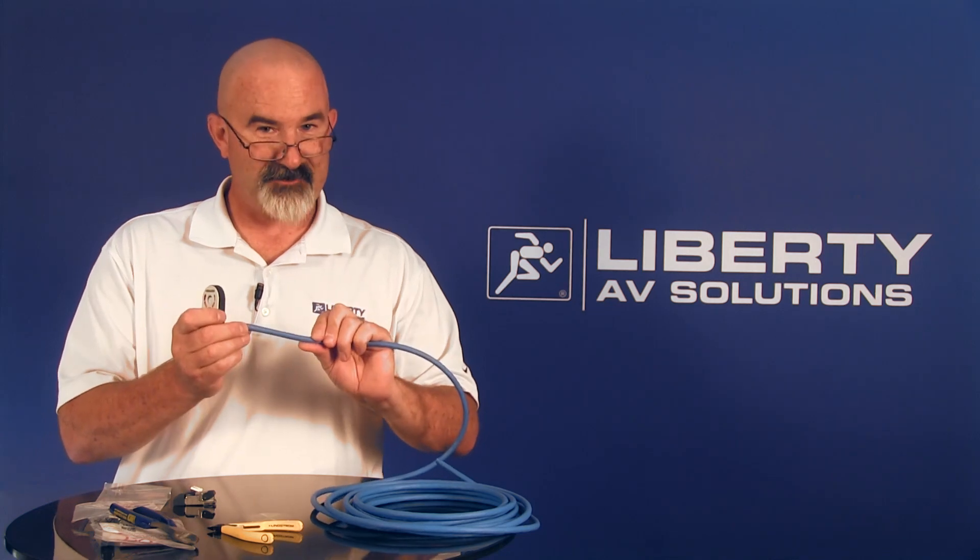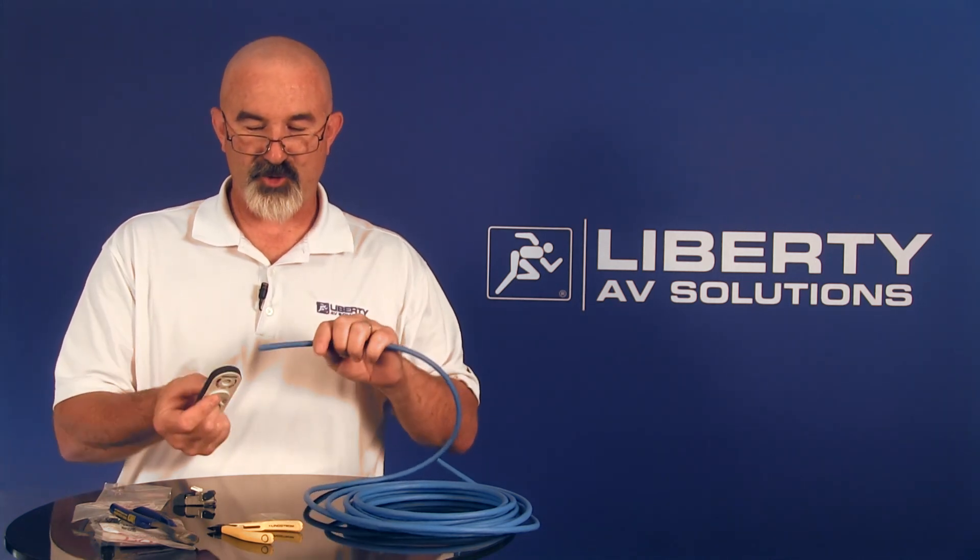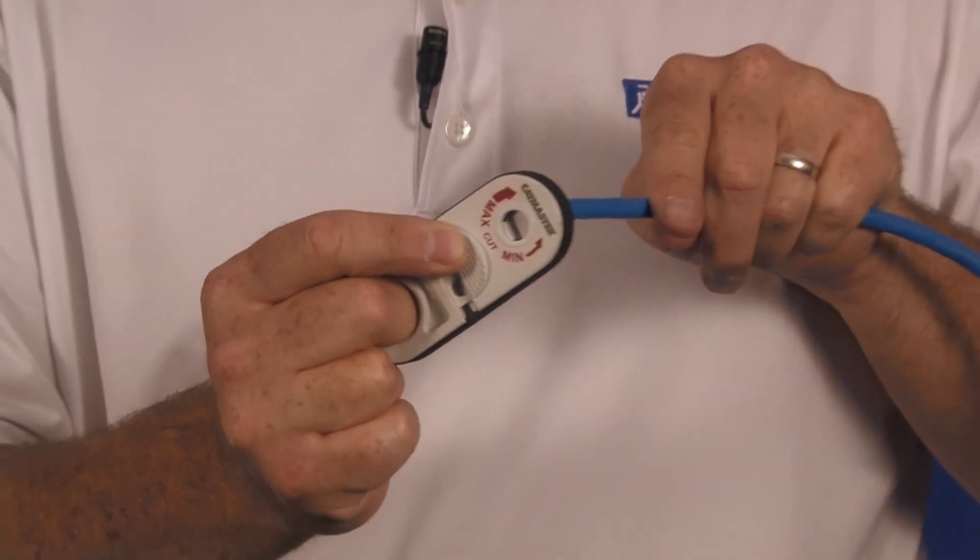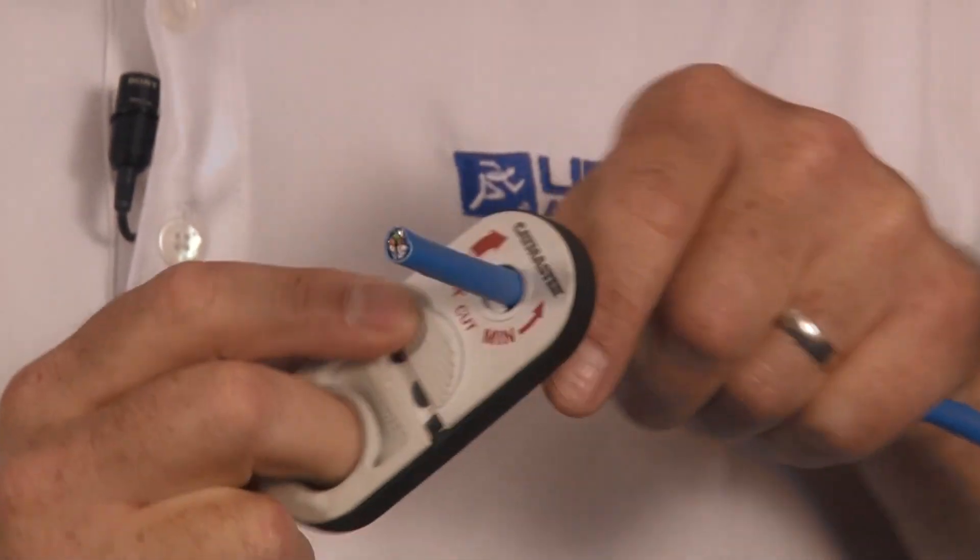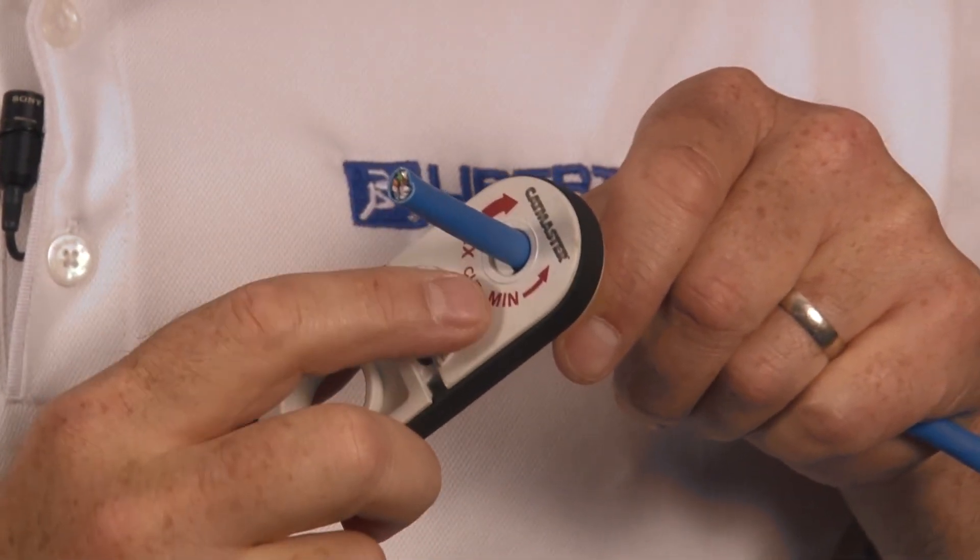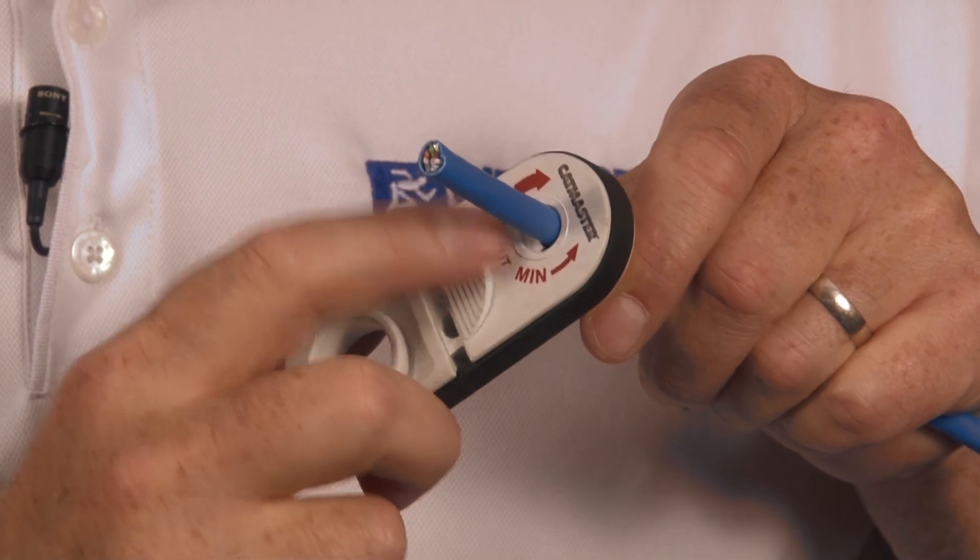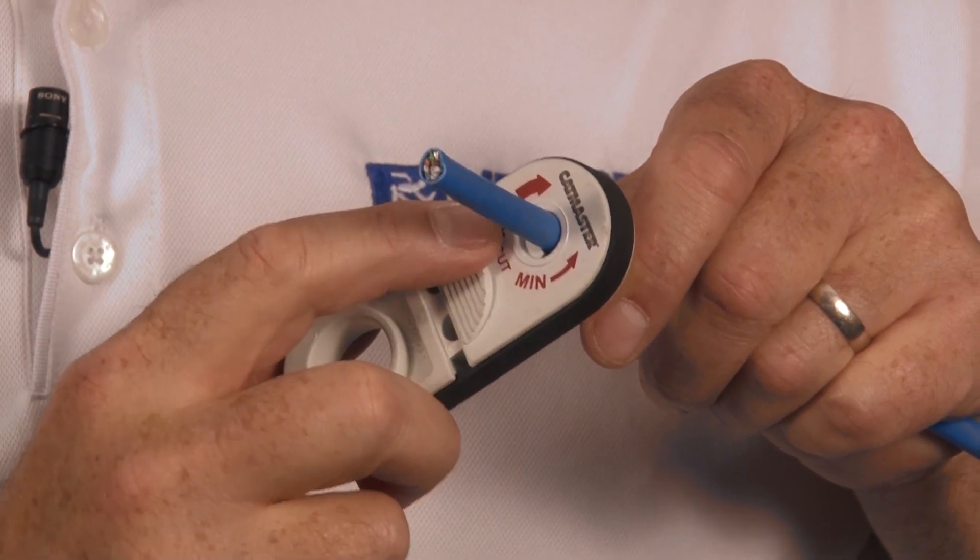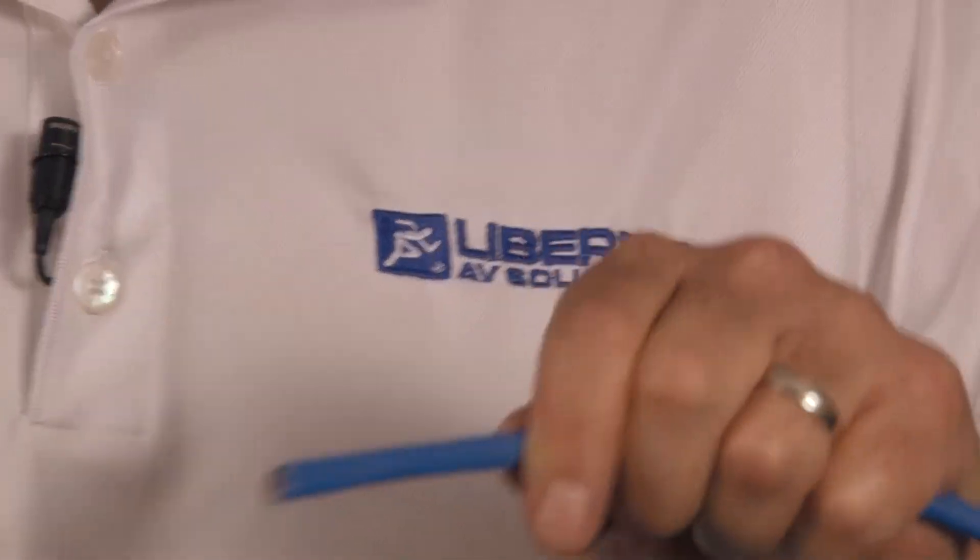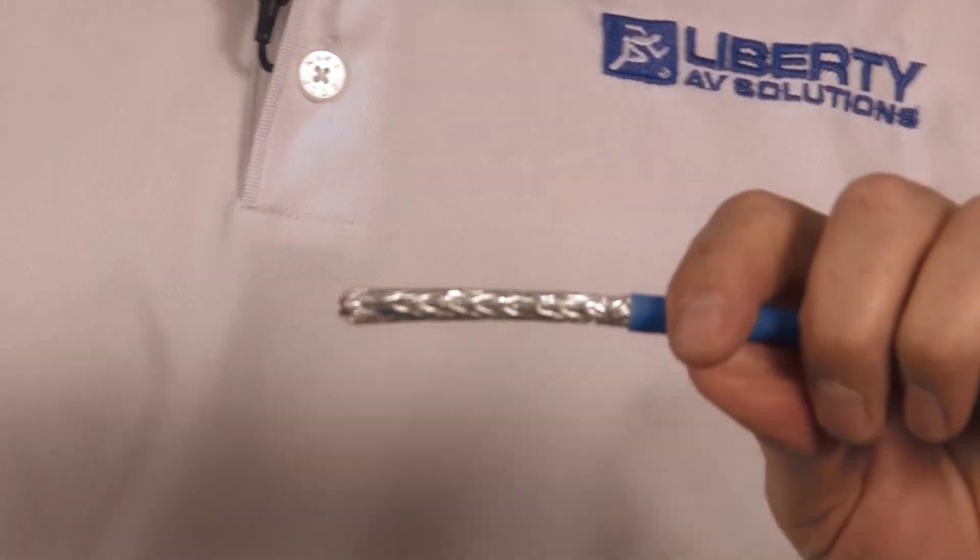So this is a Category 7 cable. I'm going to go ahead and use a strip tool, a cigar cutter type. I'm going to do about a two-inch strip. It's got a max and a min on the direction. I always want to do minimum when I'm doing shielded cables. I'll do a spin around, pop the jacket, pull it off.